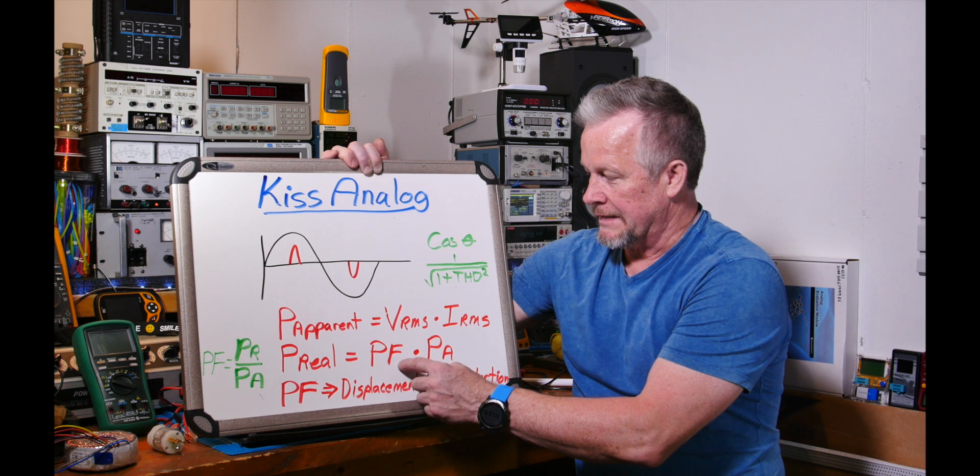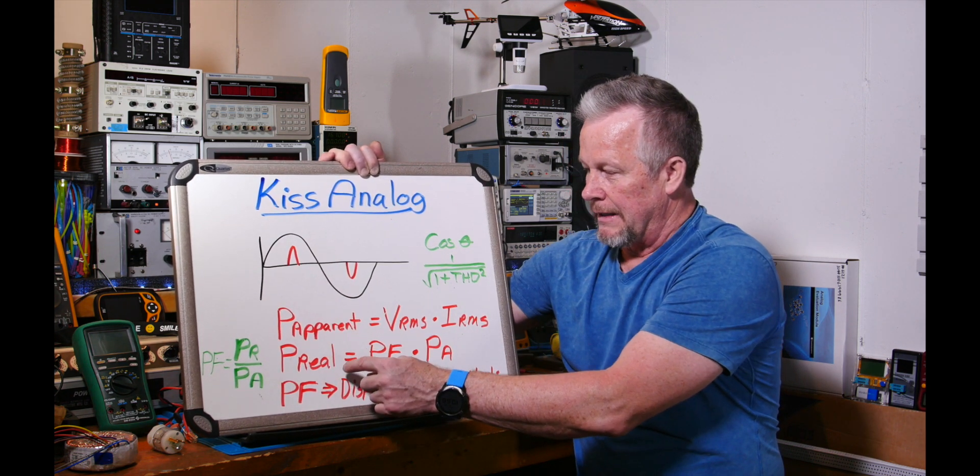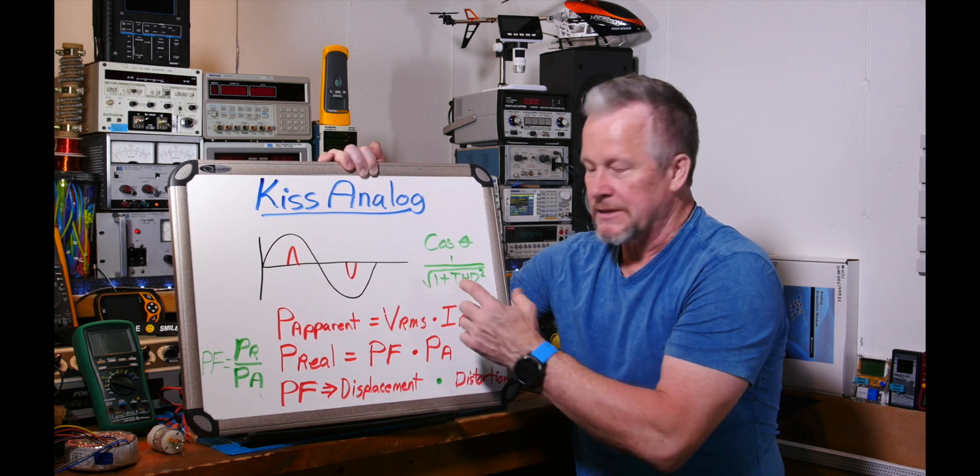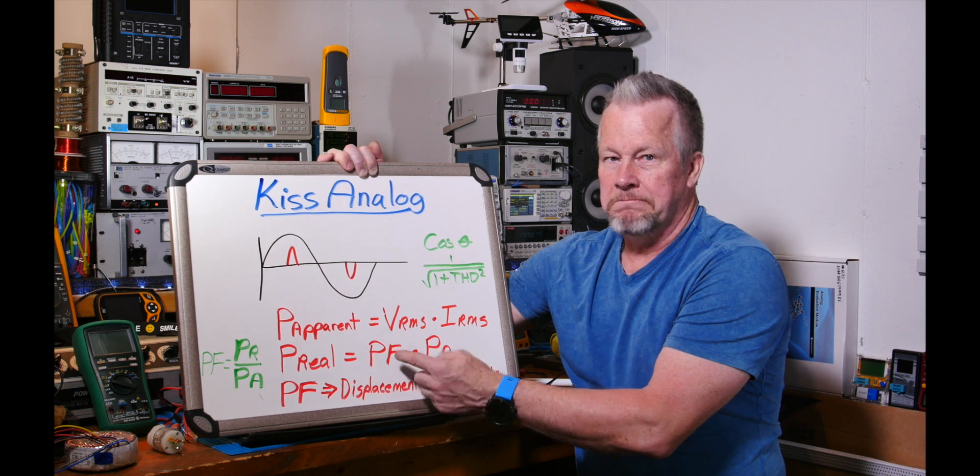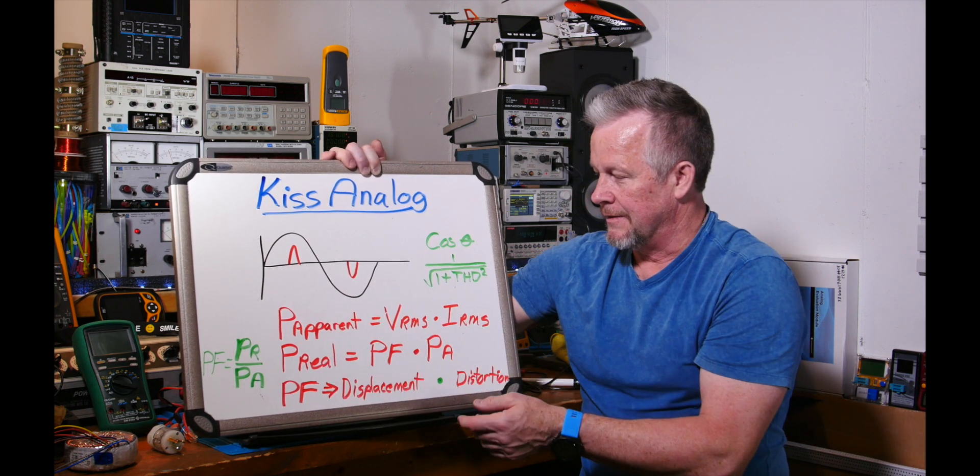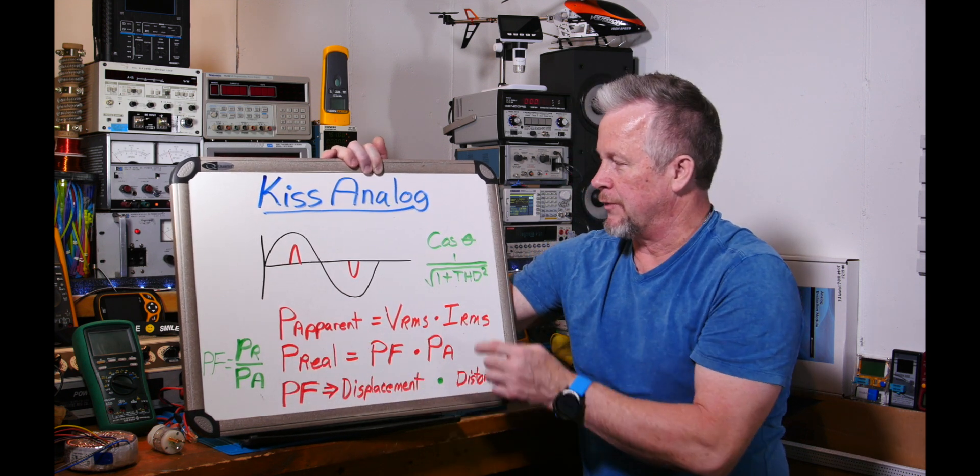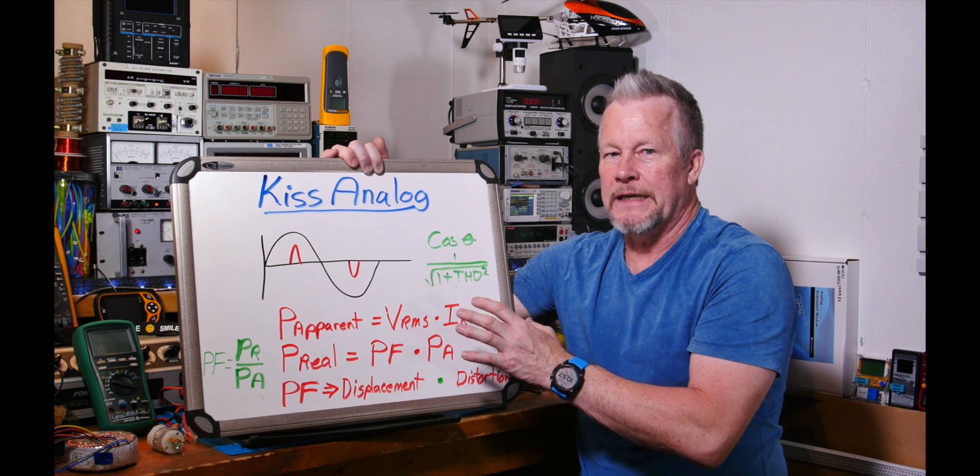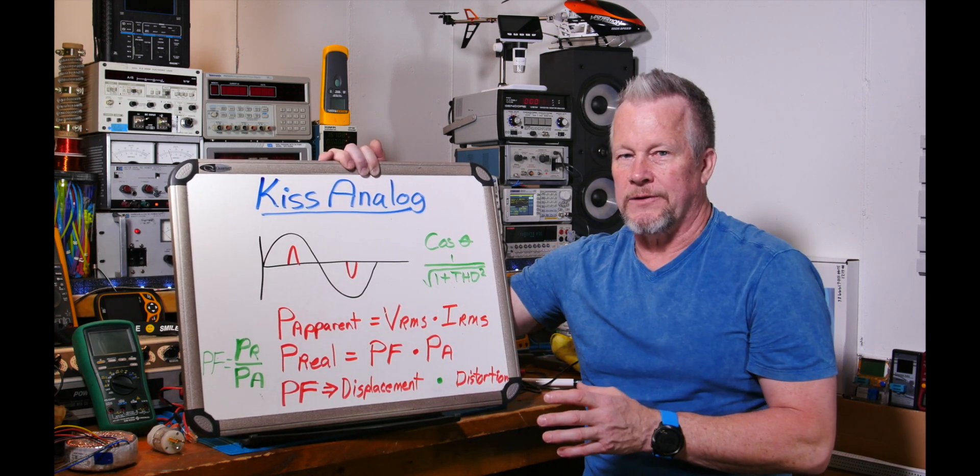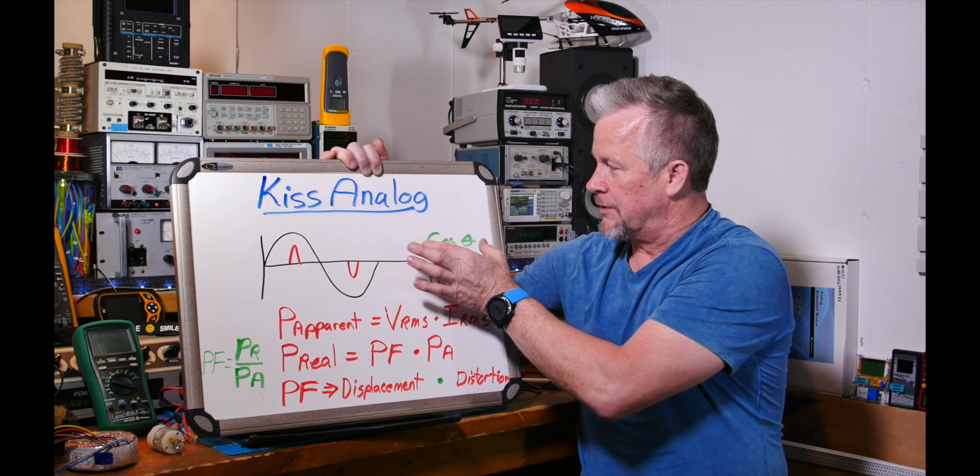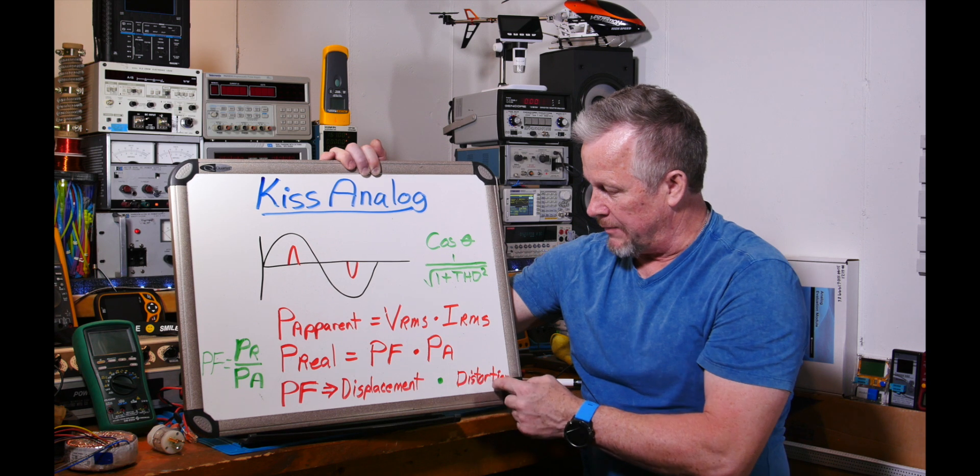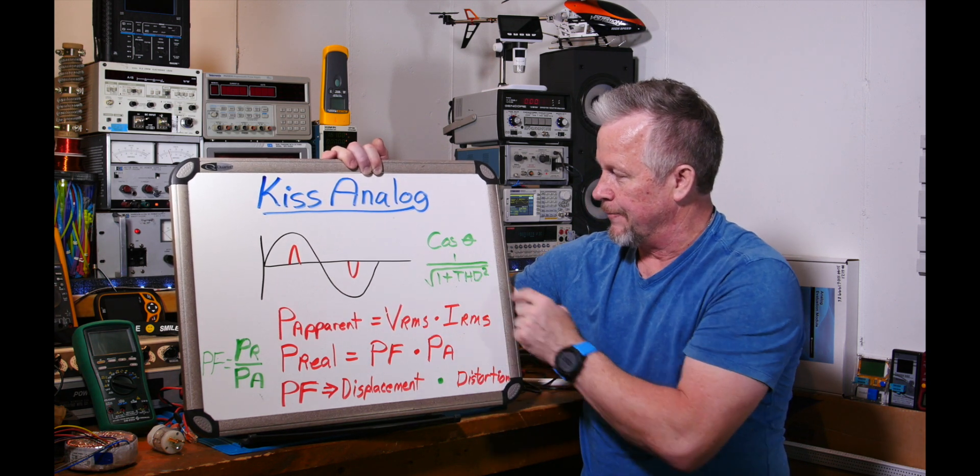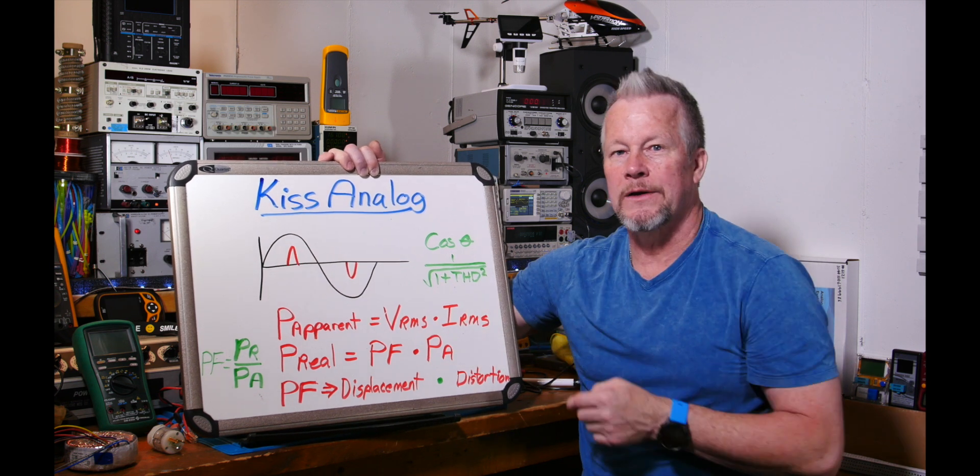Because power factor is equal to real power divided by apparent power. This is a common way to show the equation, and other ones with a cosine, but that only works if they're sinusoidal. If they're not, there's actually a distortion factor that happens too. So power factor turns into displacement, which is this, but it's also multiplied by this distortion factor, which is 1 over square root of 1 plus THD squared.